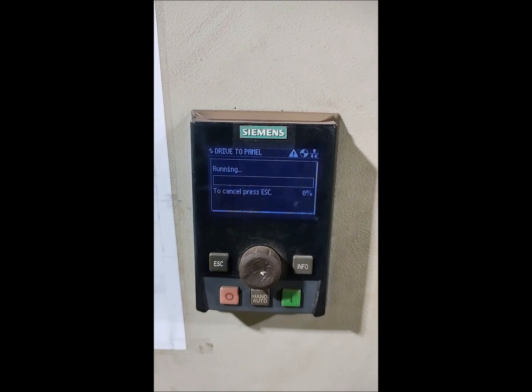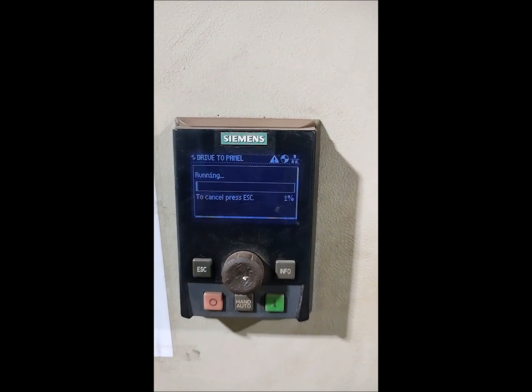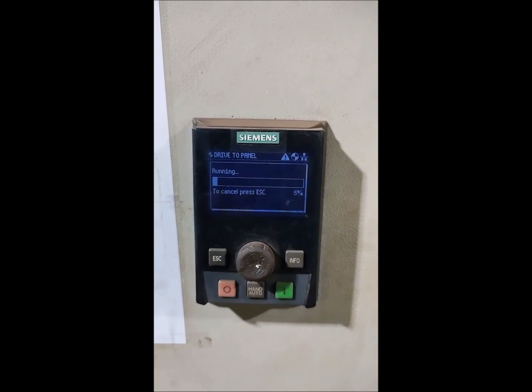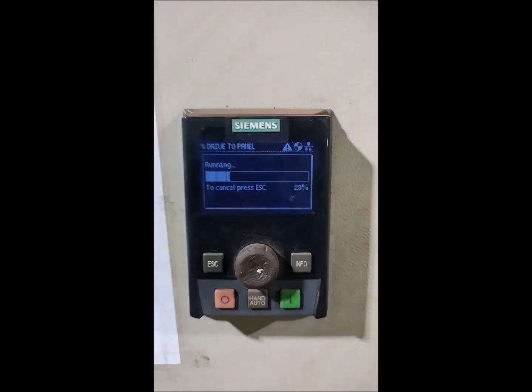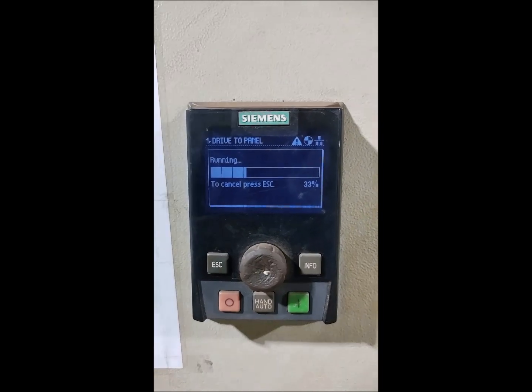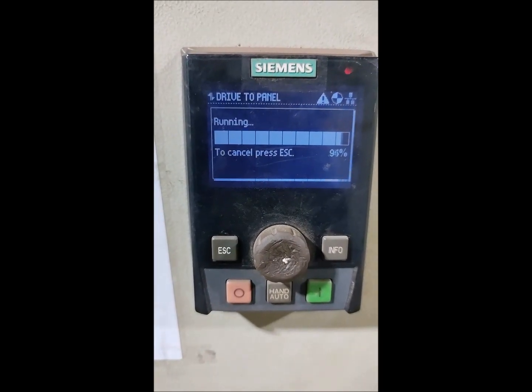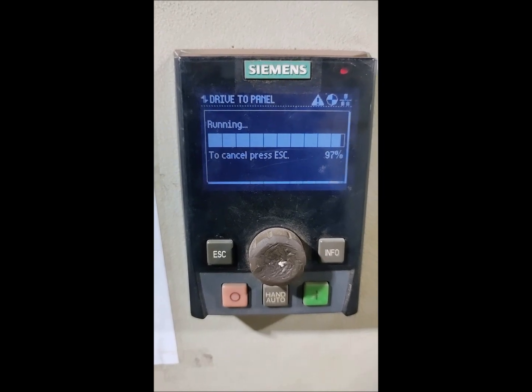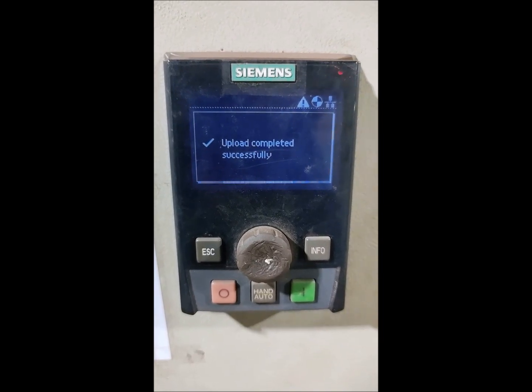So guys, why I am repeating this point is that there are two different drives. The first drive is the faulty drive that we have done the factory reset on. This is the healthy drive - another drive - and it is having the perfect, healthy program. So we have uploaded the program from the drive to this panel, and we will take this panel to the faulty drive and download the program. Upload completed.